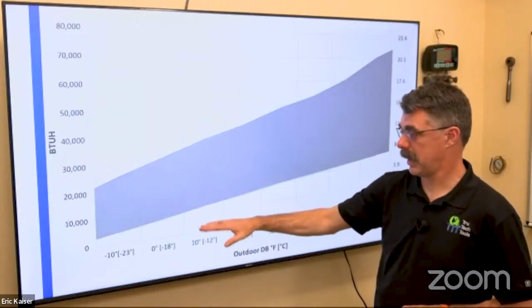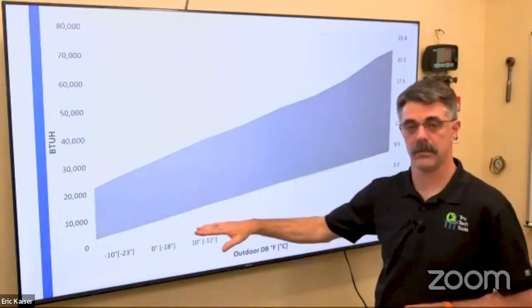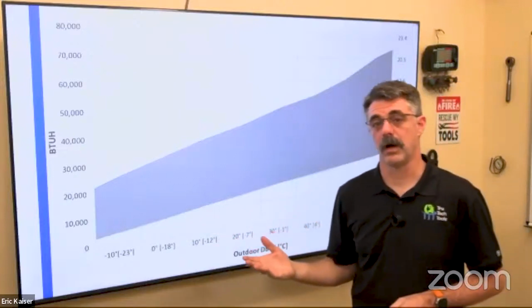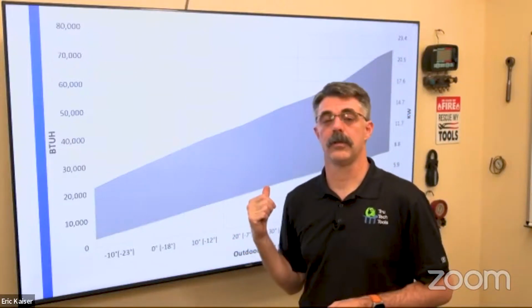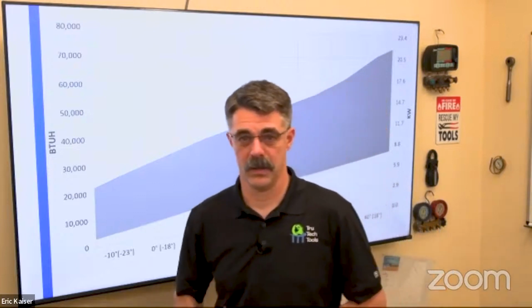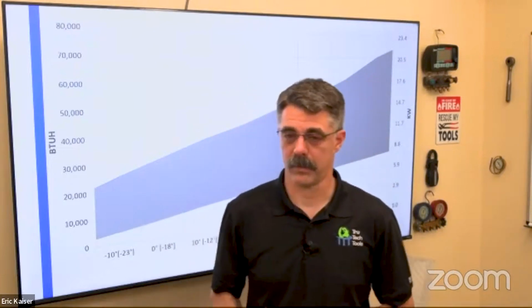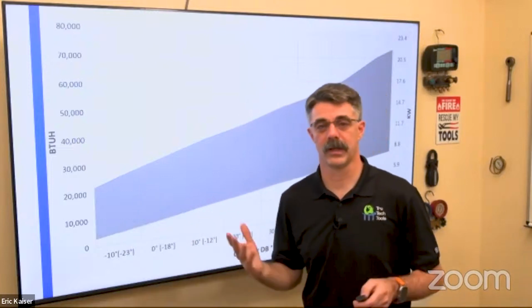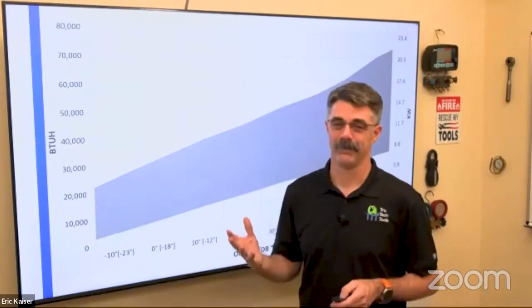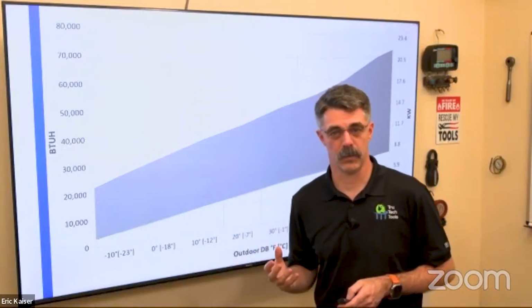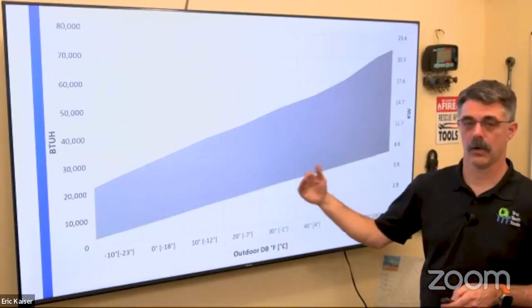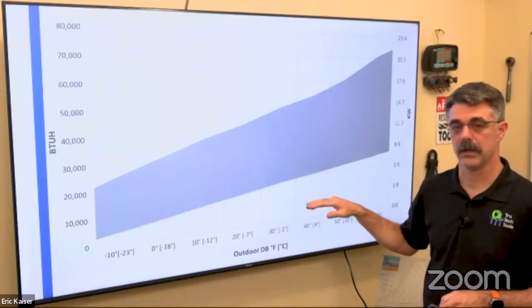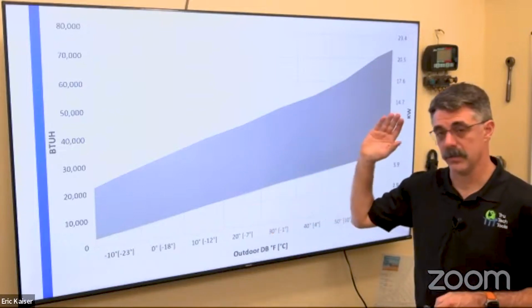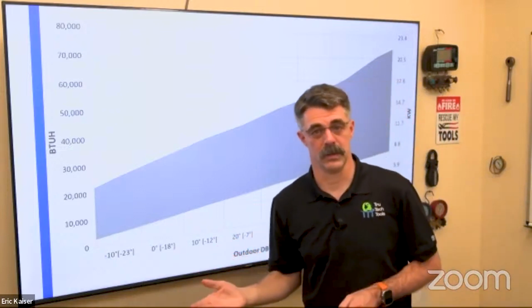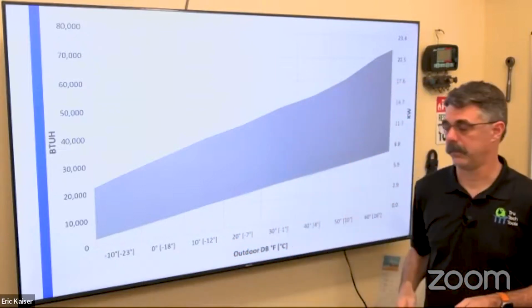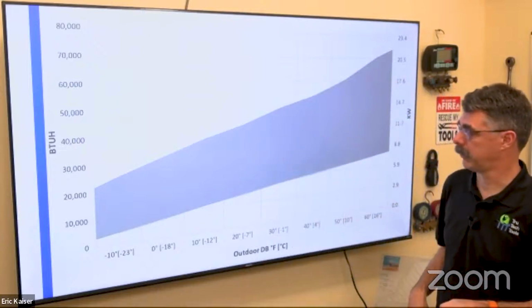Now, when we're talking about inverters, it's very important to understand they have a maximum and a minimum. So down here, if my load is underneath this line, it's going to be shut off. This is where we can get in trouble with oversizing heat pumps. I've heard a lot of people say, hey, it's an inverter, I can oversize it, I can do whatever I want with it. You really can't, right? You've got to be careful with that. Because if you oversize it too much, you end up down here below the operating range and your unit just shuts off, and then you might as well have a single stage in there because it's just going to come off and on and off and on. That's going to cause discomfort.